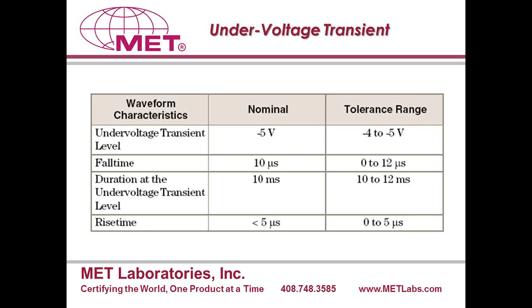Why? The first question is, why are we worried about undervoltage and overvoltage transients? The main reason is that we are talking about switching very high load currents, of the order of a couple of hundred amps to 400 amps, in practically zero time. Again, let me rephrase myself: in practically zero time, and what it means is the di/dt would be outrageously high, which will lead to numerous problems, and we'll explore them as we go through this presentation. At the same time, it's not a simple task to achieve switching of those higher load currents in the time frame of 5 microseconds or 2 microseconds, which is required for the overvoltage transient.